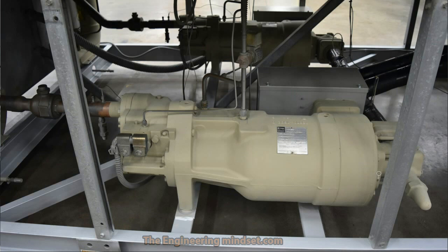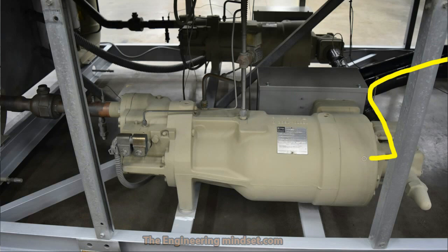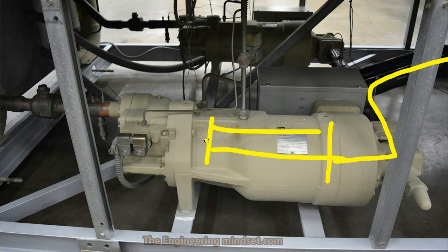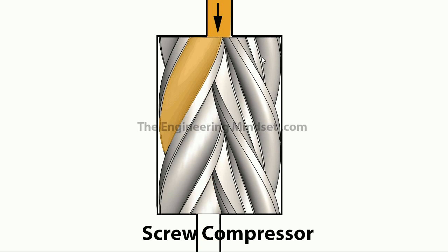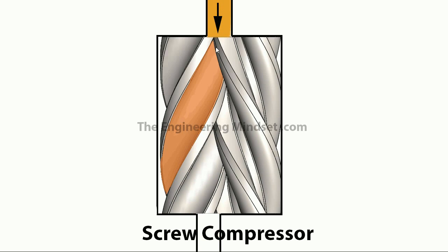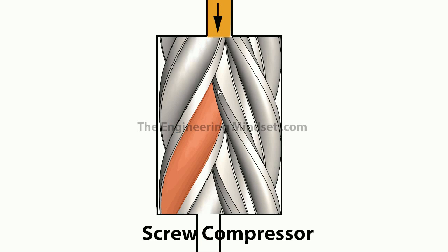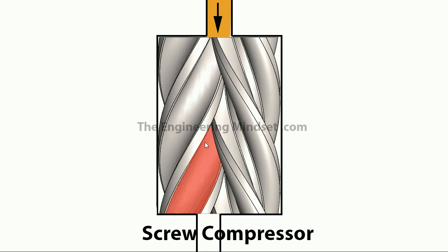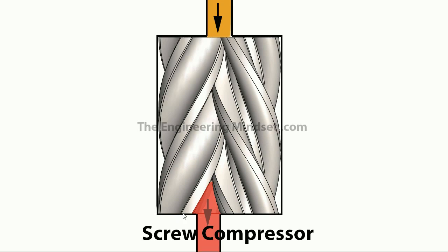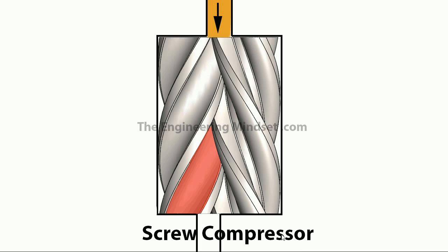These are also fairly common on air-cooled chillers. Here's another example of a smaller version with two mounted on a chiller. You can see the refrigerant flowing in and entering into the two screws inside, which we'll look at shortly. After being compressed, the refrigerant exits and heads off to the condenser. Inside, the refrigerant enters and fills the chamber, and that chamber slowly gets compressed by the next screw passing along, compressing the refrigerant to a very small point, then discharging it off into the condenser.